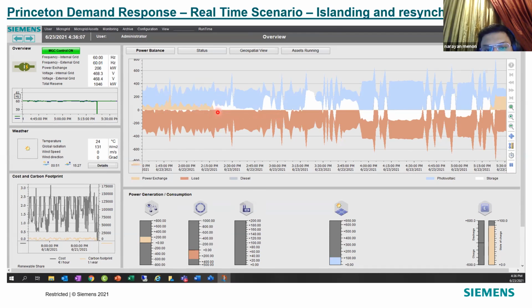From around 2:15 onward, you can also see the battery, indicated by the storage system in white - there were certain periods of excess solar power where the battery was also being charged, so the entire load was catered by the solar system while also charging the battery. This continued until the grid power came back, there was complete resynchronization, we connected back to the grid, and the battery stopped discharging.